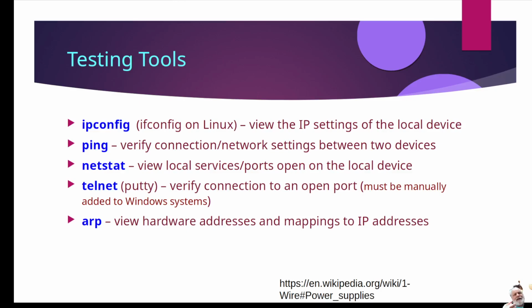So that tells you that, number one, both devices are turned on, powered up, and that they have an IP address, and they have the correct wires, and everything between the two is all correct. It doesn't tell you whether you're going through a gateway or not, if you're on the same network or not. It doesn't tell you that, but it does tell you that you can communicate with that device across the network.